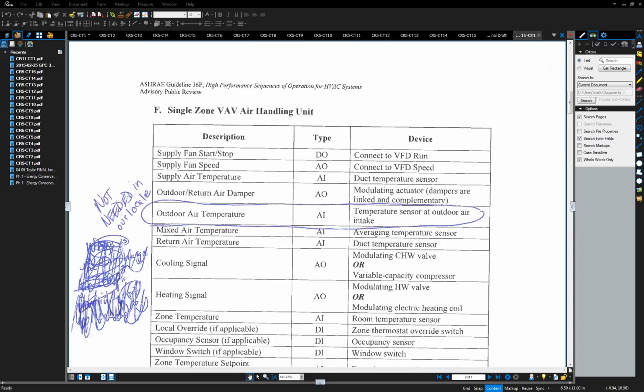Yeah, I don't think anybody would disagree with you. Where you have a good outside air system sensor, we also, as our standard when we do our own controls, typically look to see if there's a NOAA weather station nearby, and we may have multiple outside air sensors at each of the air handling units, but we compare it to the NOAA reading and do a maintenance alarm if they're far off of what the local weather station has. The same would be true if we had a high quality, like an aspirated outside air sensor with a radiation shield or something on the building itself. We would compare all of the other air handling unit intakes to that to see if they were in fact drifting and be able to alarm on it.